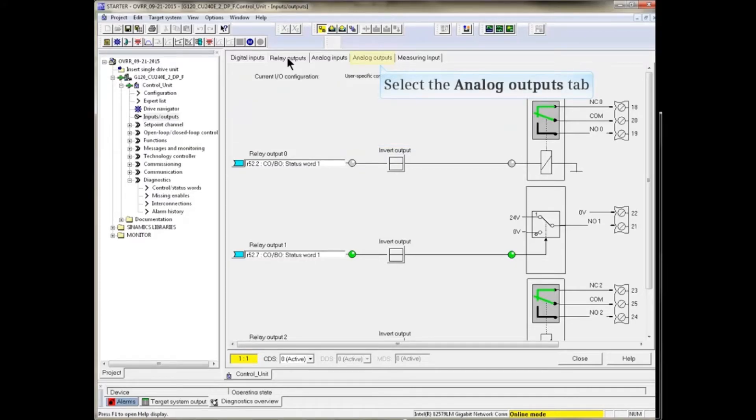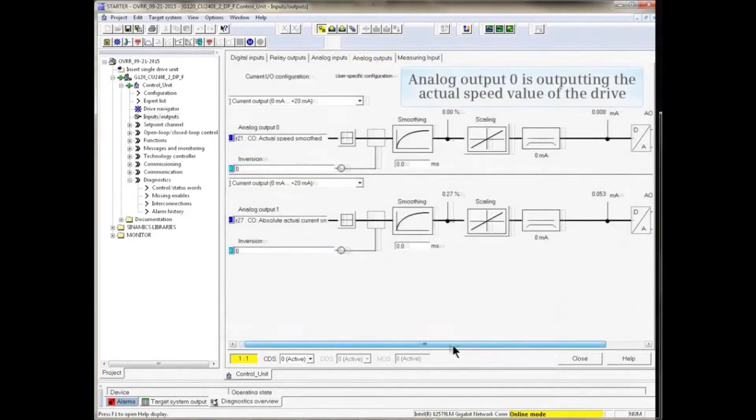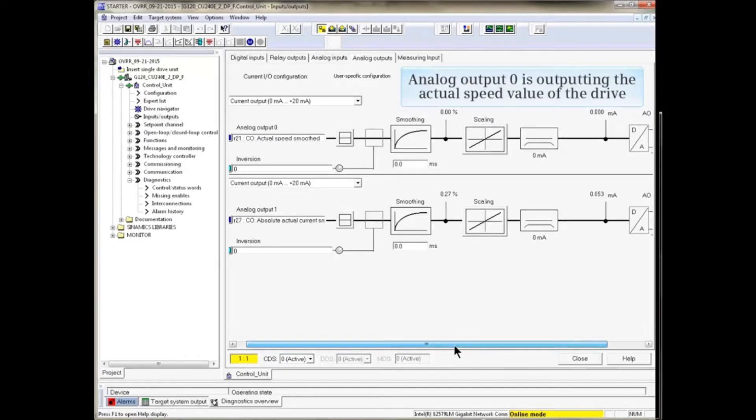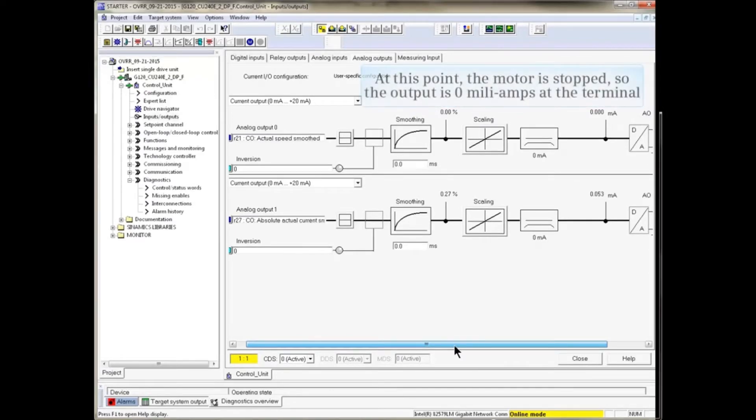Now let's look at the Analog Outputs. Analog Output 0 in the example is outputting the actual speed value of the drive. At this point the motor is stopped, so the output is 0 milliamps at the terminal.